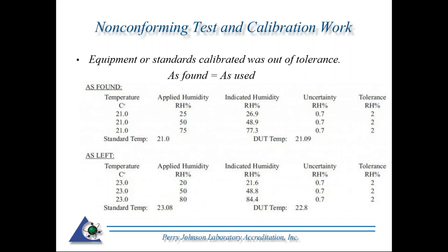So how far back do you need to go? Unless you have an intermediate check on the equipment, as far as you know, it could have gone out of tolerance the day you got it back from the previous calibration, or it could have gone out of calibration the day before you sent it off. Hence, you have a year's worth of investigations to do, unless you had something in place, i.e.